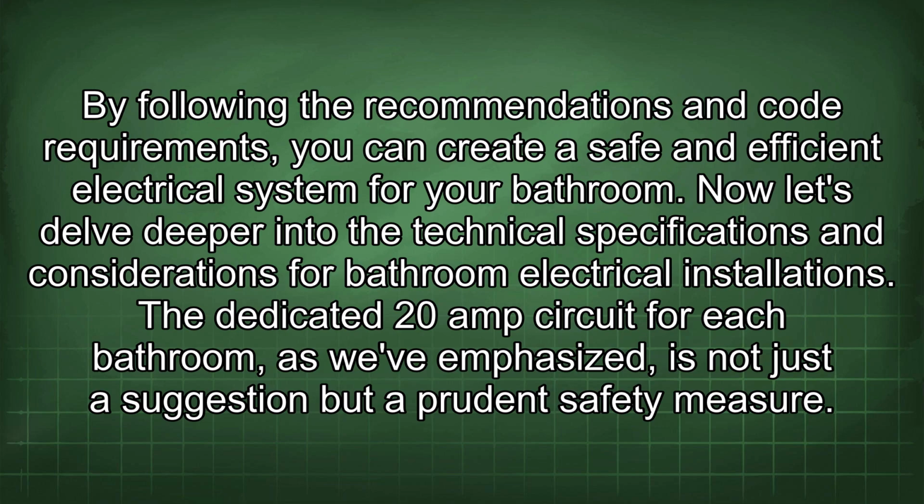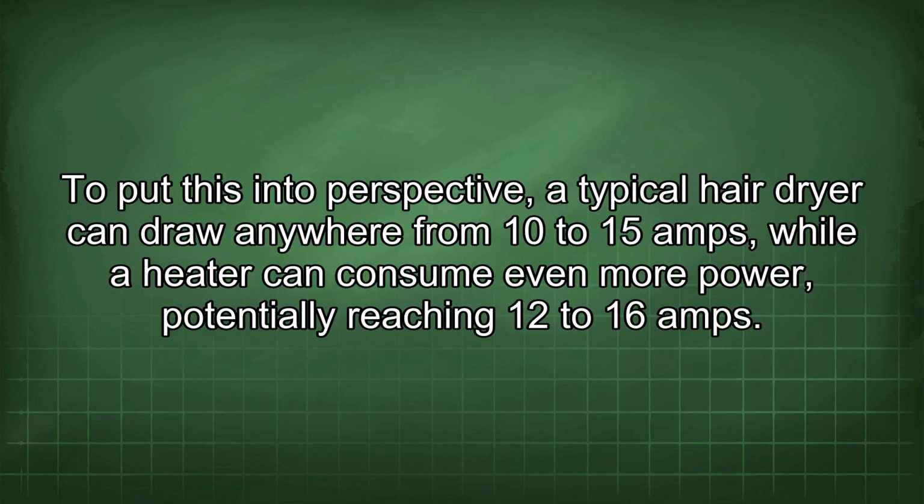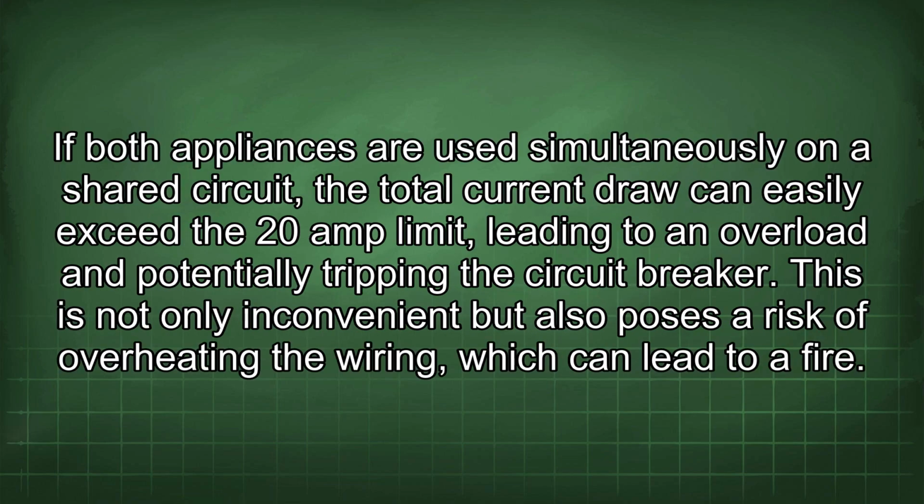The dedicated 20 amp circuit for each bathroom, as we've emphasized, is not just a suggestion but a prudent safety measure. To put this into perspective, a typical hairdryer can draw anywhere from 10 to 15 amps, while a heater can consume even more power, potentially reaching 12 to 16 amps. If both appliances are used simultaneously on a shared circuit, the total current draw can easily exceed the 20 amp limit, leading to an overload and potentially tripping the circuit breaker. This is not only inconvenient but also poses a risk of overheating the wiring, which can lead to a fire.